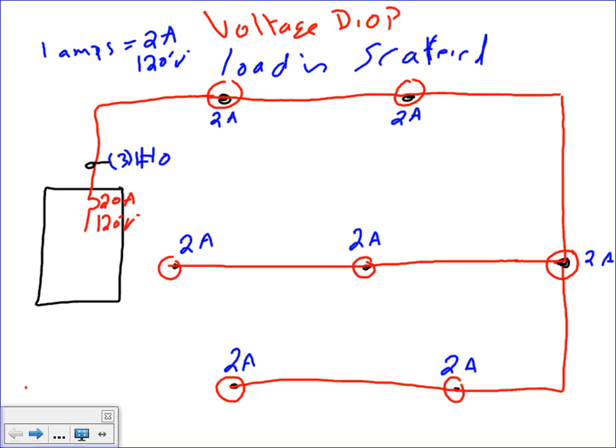You guys agree with me that for each one of these, the parking lot cable is coming to an enclosure. You tie number 12, or probably number 10, all the way up to the top of the pole to connect your lights. So we're just looking at the bottom of the pole. That's what we care about most of the time. From here to the top of the pole, guys, you don't have a problem with 2 amps. Okay, see where the 2 amps are coming from? Every dot and circle here is actually a pole sitting with a lighting fixture.